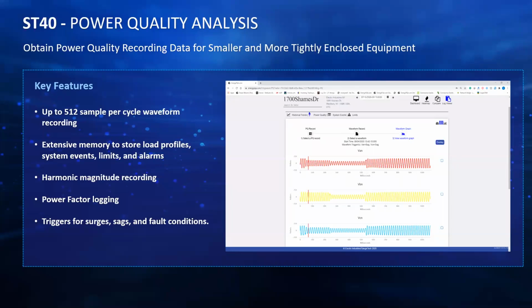In addition to revenue accuracy, we have power quality, we have harmonics monitoring capabilities, we have waveform capture. We can capture up to 512 samples per cycle on all 6 channels. Your A, B, and C phase voltages and currents will all be captured no matter which leg or phase has the event. We record up to the 40th order of harmonics, both magnitudes and angles. We'll record power factor.